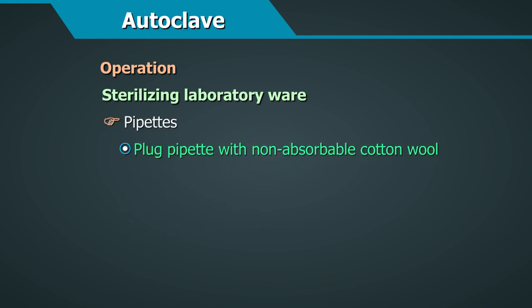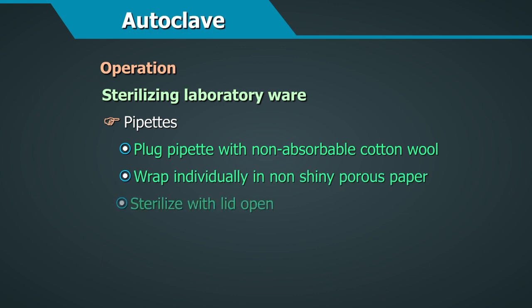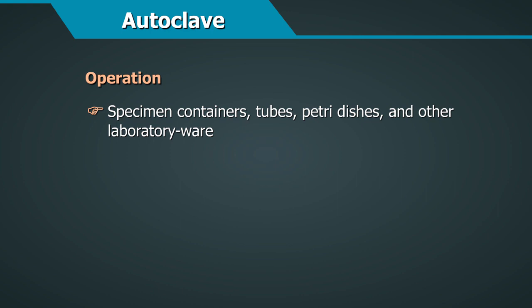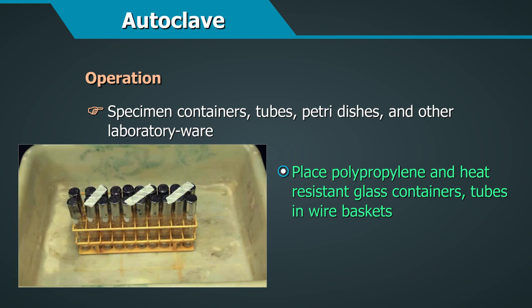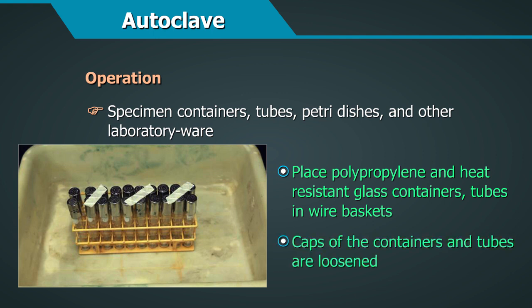Pipettes. Plug glass or polypropylene pipettes with non-absorbent cotton wool and wrap individually in non-shiny porous bag, example, X-ray wrapping paper, or place in a metal or polypropylene canister. Leave the top off during autoclaving. Specimen containers, tubes, petri dishes, and other laboratory ware. Place polypropylene and heat-resistant glass containers, tubes, and other items in wire baskets or other suitable open-sided holders. When loading, make sure the caps of the containers and tubes are loosened.